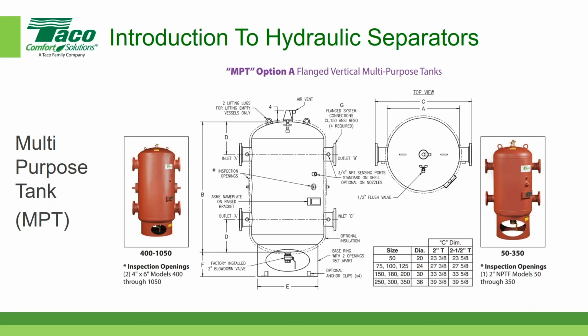Well, that volume, by the way, is not just in the buffer tank, in this case a multi-purpose tank, but it's also in the piping system. So if the piping system had a volume of, say, roughly 4,000 gallons, we would subtract that. So your buffer tank would have to be 1,000 gallons. So again, rather than putting in multiple devices, in order to keep the boiler or the chiller from short cycling, you might consider putting in a buffer tank. Most manufacturers of the chillers and boilers would recommend that. And if your piping system, in our simplified example, allowed for 4,000 gallons, but the total gallonage that you needed was 5,000, then your tank would be roughly 1,000 gallons.